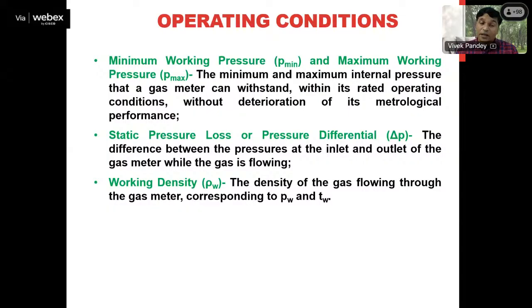Now the other parameter is working density, that is, what is the density of the gas which is passing through the gas meter at a certain time. That density should also be measured by a density measuring device.